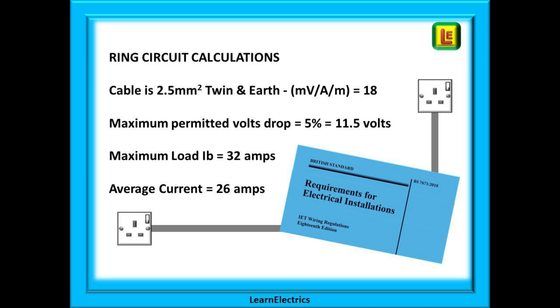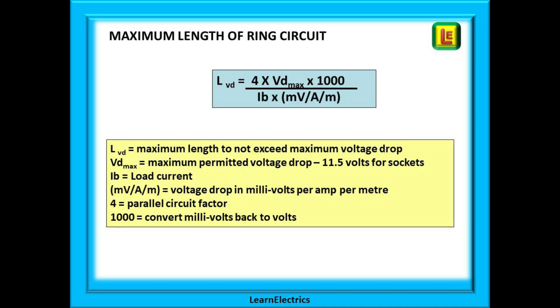We said that we would calculate maximum lengths first. This is the standard formula for calculating the maximum length of a cable that will not take us over the maximum volts drop limit. In the box below we've shown what each symbol means. LVD will be our answer, the maximum length to not exceed the maximum voltage drop. VD max is the maximum permitted voltage drop, 11.5 volts for sockets. IB is the load current. MVAM, as we said earlier, is the voltage drop in millivolts per amp per meter. 4 is the parallel circuit factor we calculated earlier, and 1000 is used to convert millivolts back to volts.